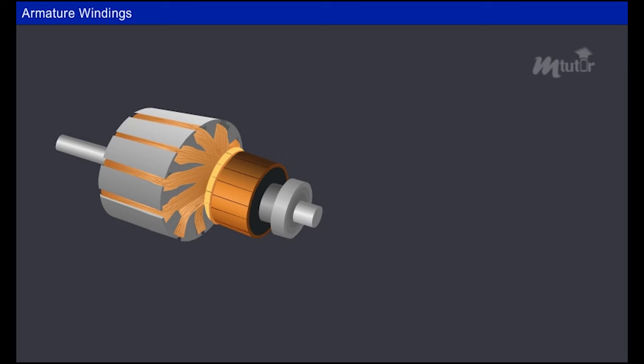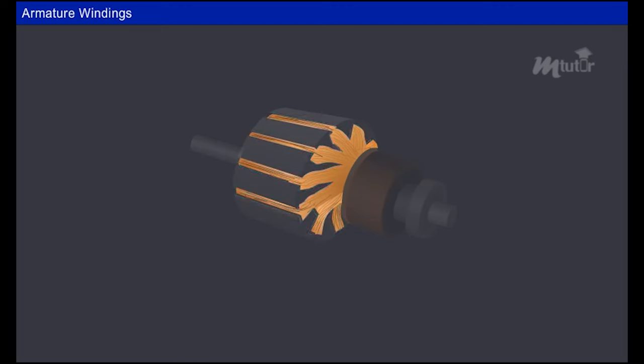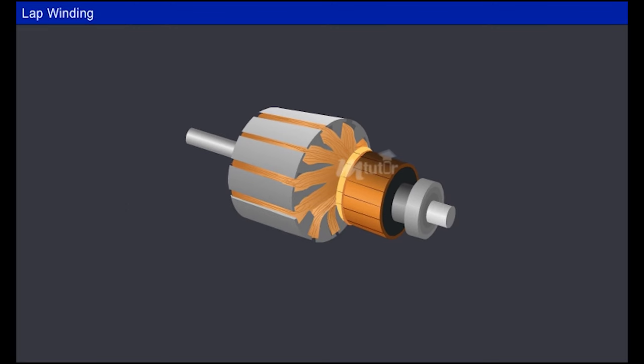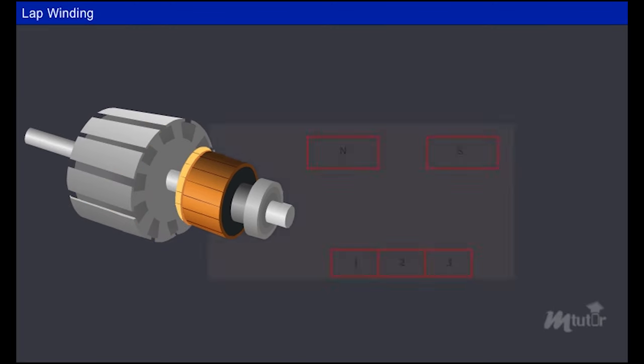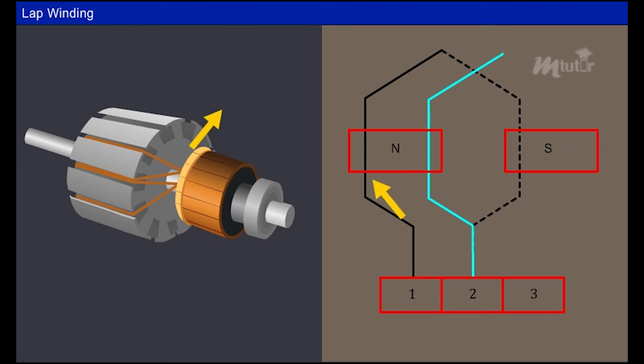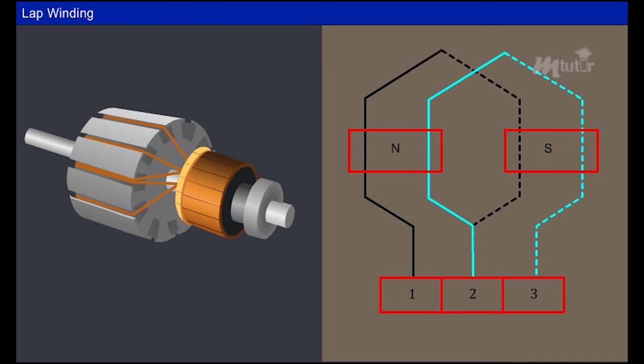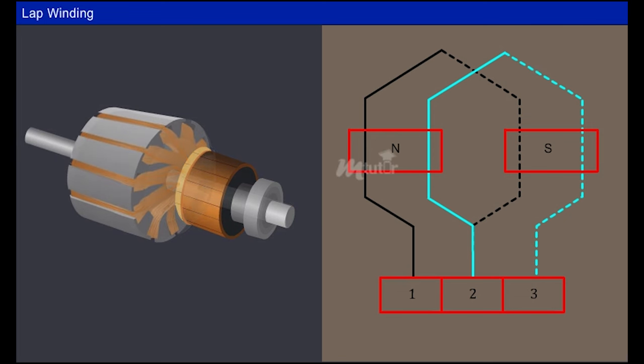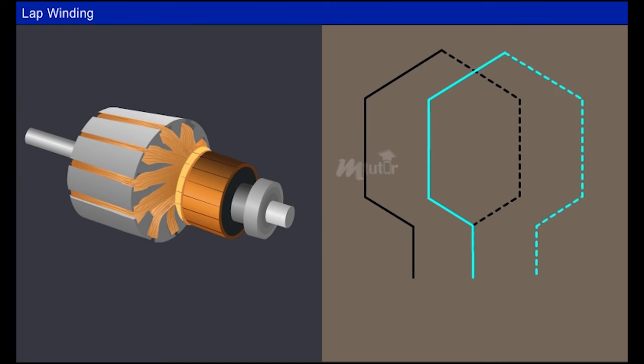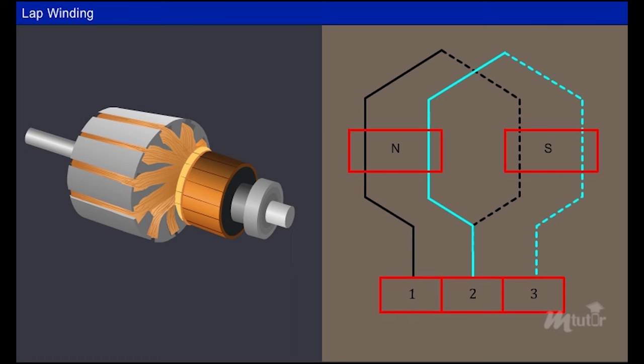The armature windings can be categorized into two types depending on their winding arrangement and connection to the commutator: lap winding and wave winding. In lap winding, the completing side or back end of a coil is connected to a commutator segment and to the start or front end side of the successive coil under the same pole pair. This process continues for the remaining coils. The coils overlap each other in this winding method, hence the name lap winding.